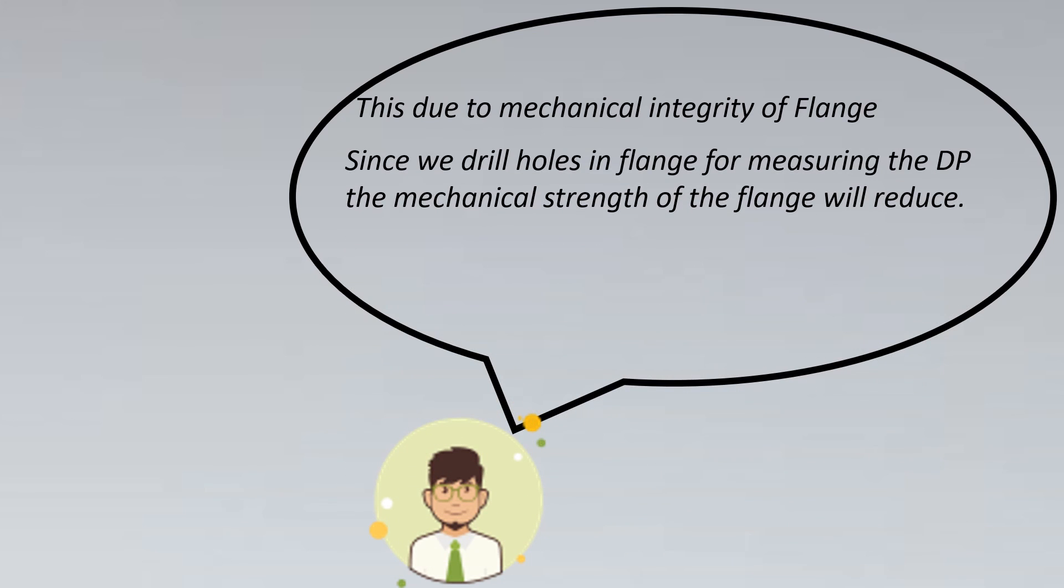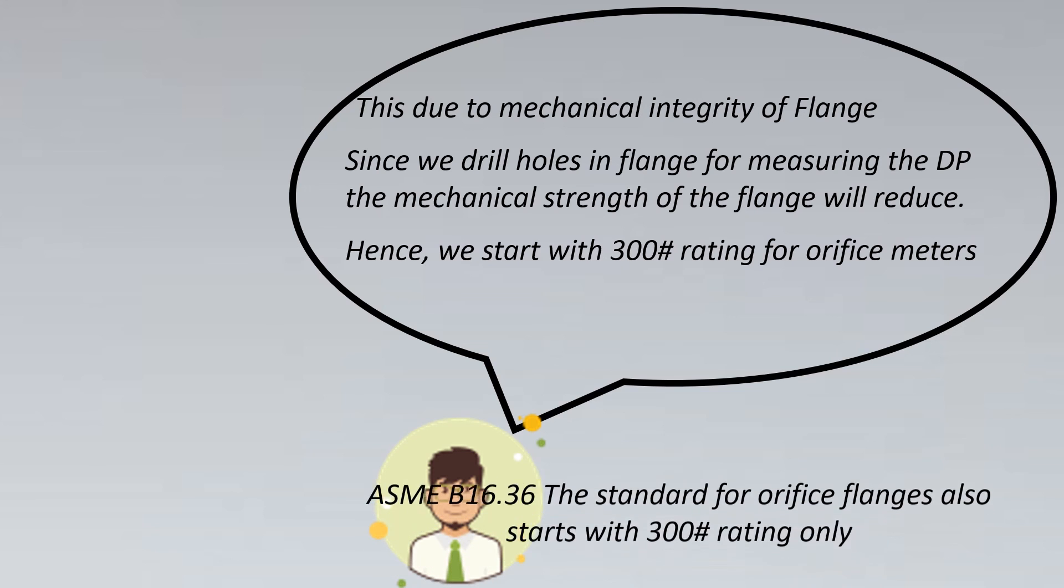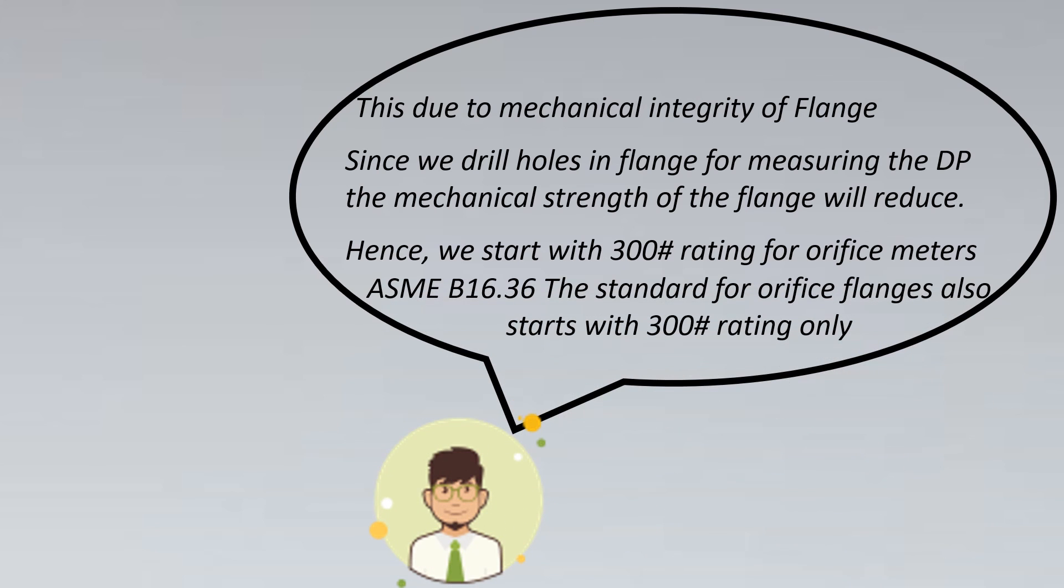Second is, since we drill holes in the flanges for measuring this DP, the overall strength of your flange will reduce dramatically, and thus 150 rating might not be suitable. Hence we usually start with 300 rating for orifice meters. But for restriction orifice meters where there is no tapping to be drilled, you might see 150 rating for those cases also. If you want to prove the standard which is ASME B16.36, the standard for orifice flanges also starts with 300 rating only, so we can have a standard which supports this understanding.